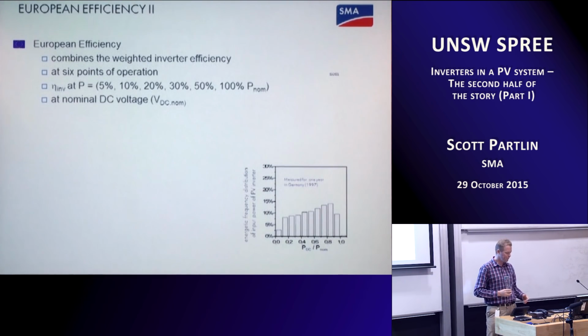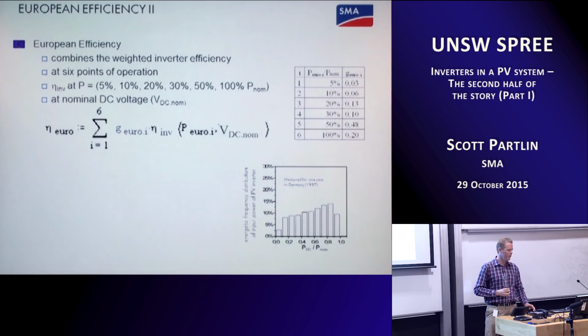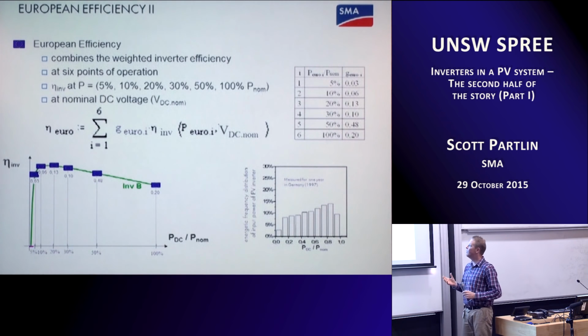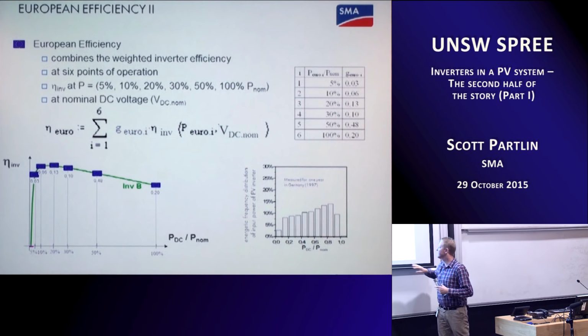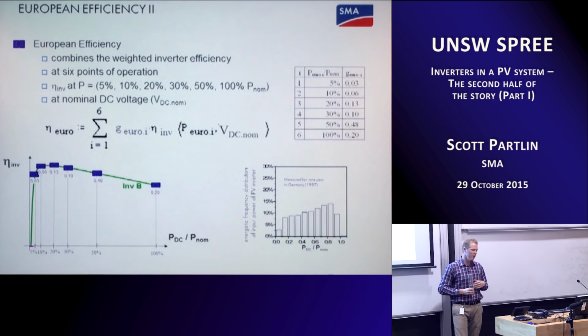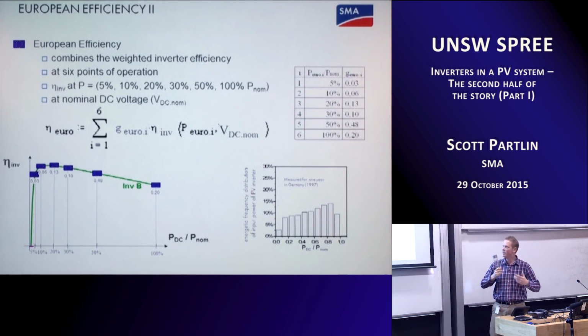for their individual plant. So the way the European efficiency works is that it knows that a PV inverter never operates at 100% power for 100% of the year. If you looked at the output power of an inverter as it relates to the PV, this is approximately the distribution that you would get. About 50% of the time it's operating above 50% power, and then the rest of the time it's below 50% power. And so with the CEC, with the European efficiency, they try to weight each of those according to this table here to come out with a lumped efficiency number for the benefit of the system developer.